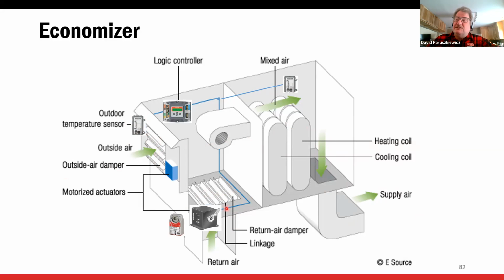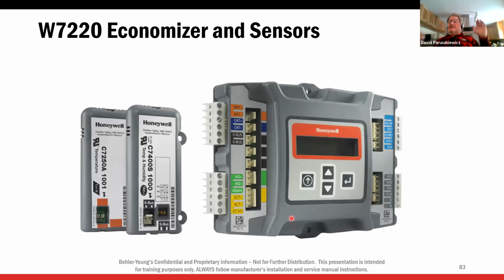Now, on a 2-stage unit, if the outdoor air conditions are better than indoor air conditions, and we open the economizer and we still don't cool enough, we can actually bring the mechanical cooling on with the economizer. We're going to dive into that a little bit. Now, the new Jade controller: you guys have only been around a couple of years, so this is probably all you've seen so far, but there was an older style prior to the 7220 Jade.